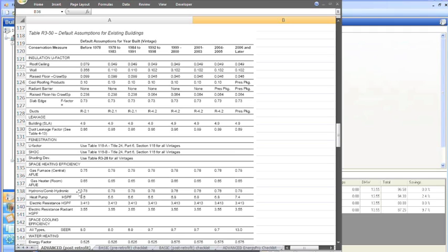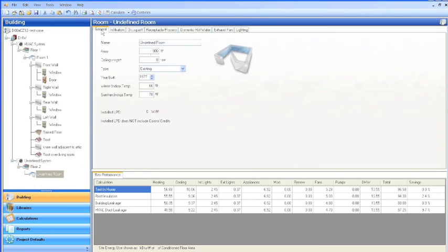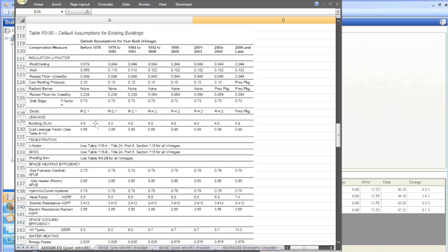Now, what if you have that and you want to estimate an insulation value because it's got something there? Maybe it's asbestos-wrapped ductwork. The default is, I believe, on here. Let me double check because I can. If it's on here, that would be easier than me just telling you. Oh, there it is, 2.1. If you don't know what it is, it's 2.1. So if that's the situation, use the vintage tables.